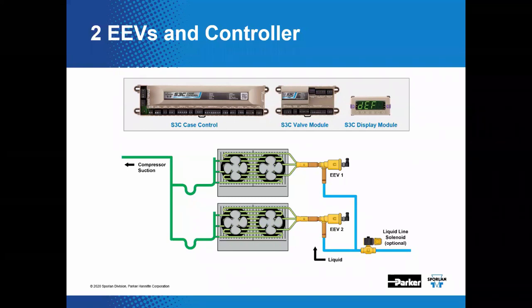The valve module is essentially an extension of the case controller and expands the controller's capabilities. Here's the valve module right here. This provides for additional inputs and outputs, like the control of perhaps 2 EEVs or 1 EEV and 1 electric EPR. In this case, it is needed for the second EEV. The case controller will control the typical case functions, collect the desired sensor inputs and drive EEV1, as you see here in this example. The valve module will collect the necessary inputs for the second evaporator and drive EEV2.